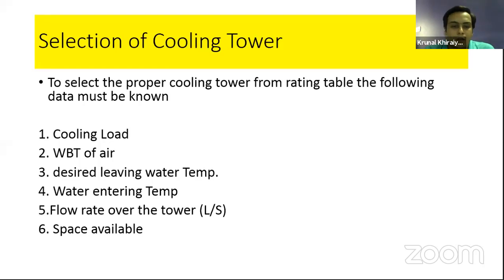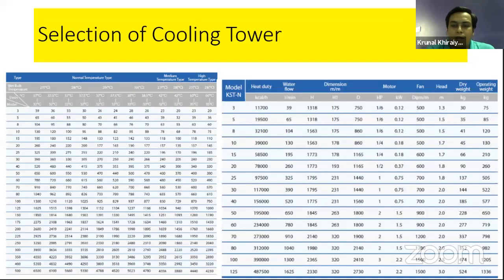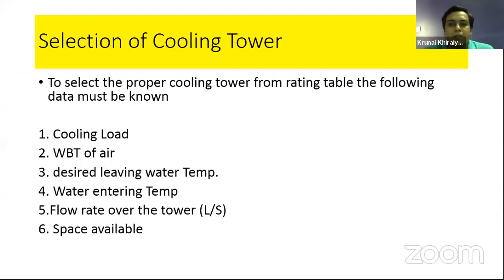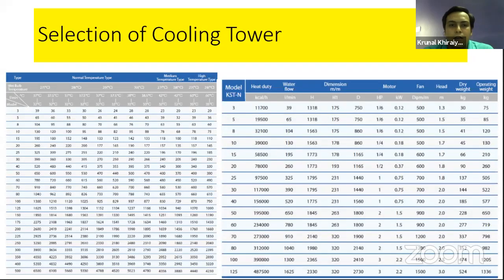Now we go to the next step, how you select using the data. With the help of the available data, you need to go with a catalog from different suppliers. Here one important table is given. If you look at the table, the type is there, the wet bulb temperature is given, then the medium temperatures, high temperatures and low temperatures. Then a model number is given. So using this first table, you can select the tower.